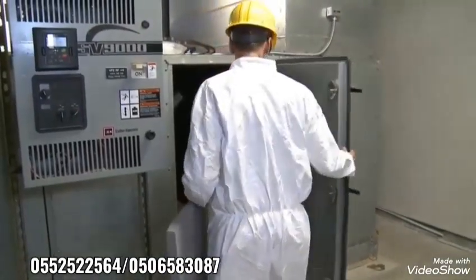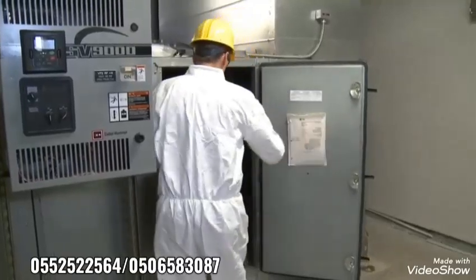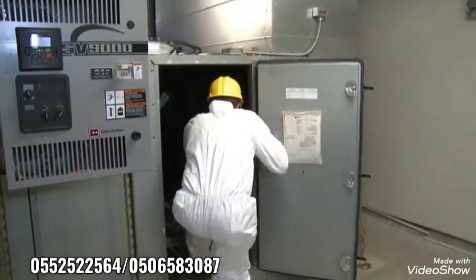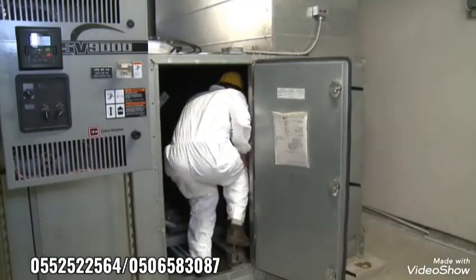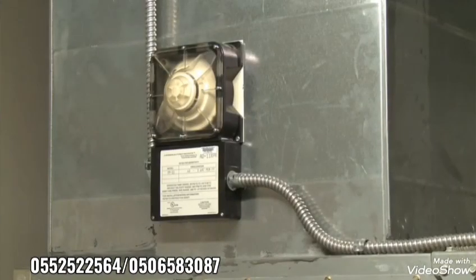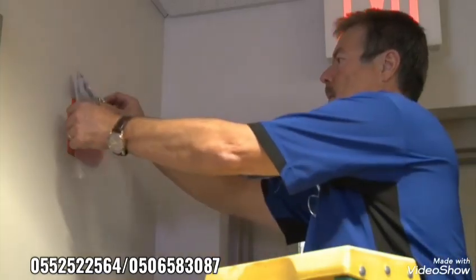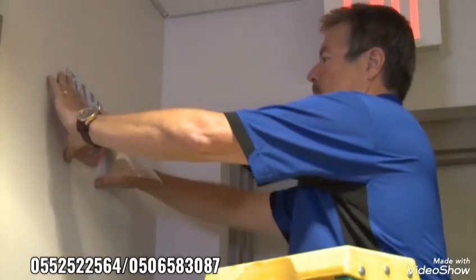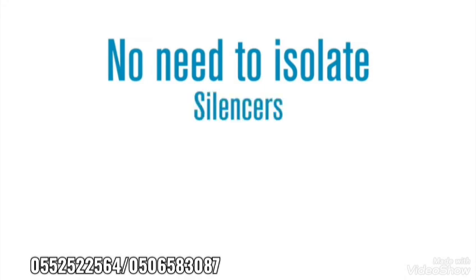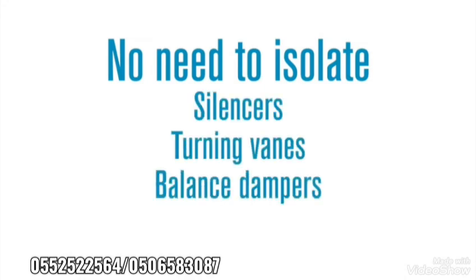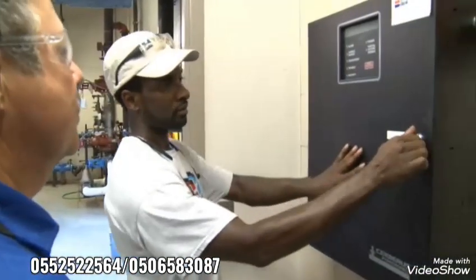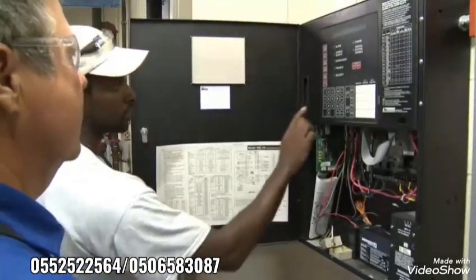Air handling units must also be blocked with foam or other materials in order to protect sensitive mechanical components from the sealing process. Smoke detectors and sensors in the ductwork and throughout the building are protected to prevent contact with the sealant material. It is not necessary to isolate silencers, turning vanes, balance dampers, or fire dampers because the sealant will not adhere to them. Fire alarms in the immediate project area are temporarily disabled to prevent false alarms.